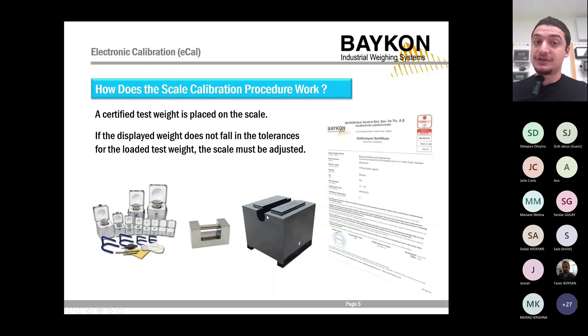So what are the steps? They're as follows. So initially, a process that we call zero adjustment is applied to the scale. We can think of this as teaching the scale what zero means. It is done when there is no weight on the scale whatsoever. The scale learns that there is no weight on it in the current state. And then we perform what we call span adjustment, where we teach the scale the maximum capacity that we will be using the scale for. An approved weight is placed on the scale, and the scale learns how many kilograms it currently weighs. This is something legal. I'm legally speaking here. It is recommended that we choose the weight to be selected that we are going to be using to calibrate that equipment.